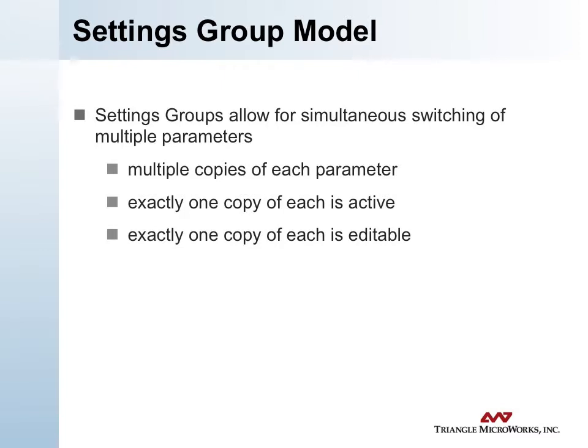Exactly one copy of each parameter is active at a time and one copy is editable. The client can have an active group running, modify the settings within the editable group, and then later make that editable group become active. This model is meant for things like relays where you have to set a group of parameters simultaneously — you can't set them individually; you need to set them as a bank or group for the process logic to operate correctly.